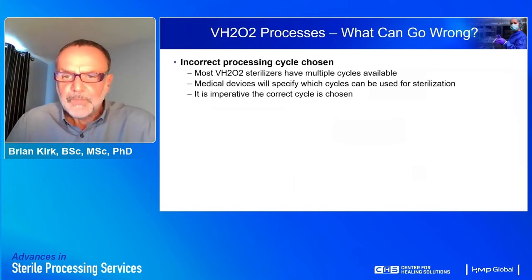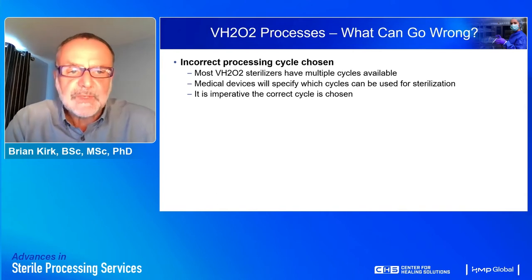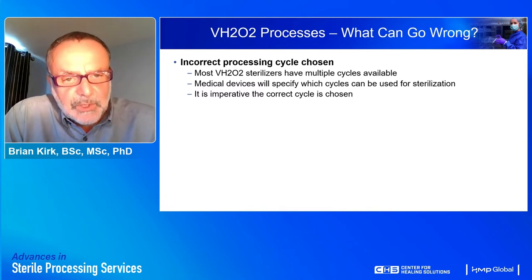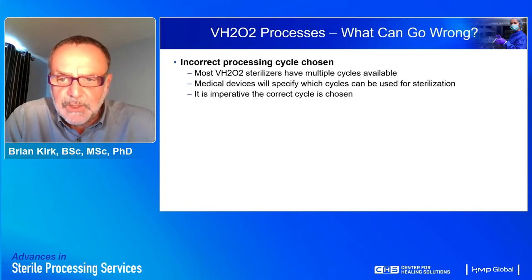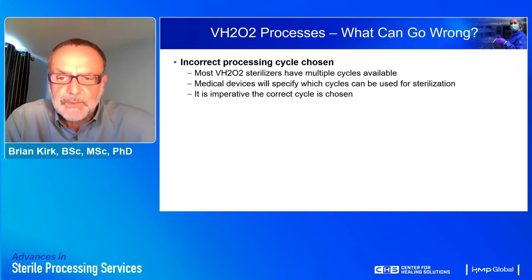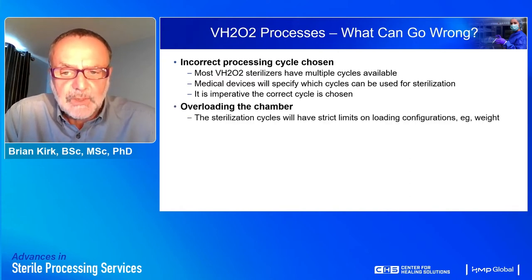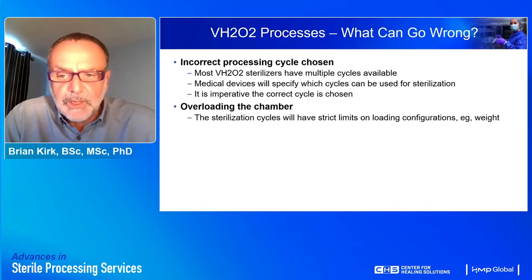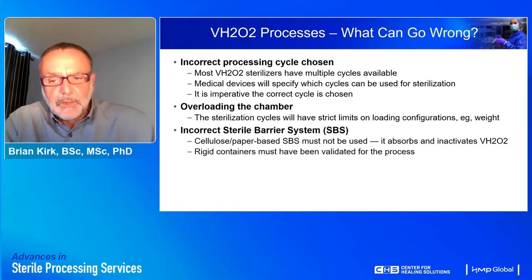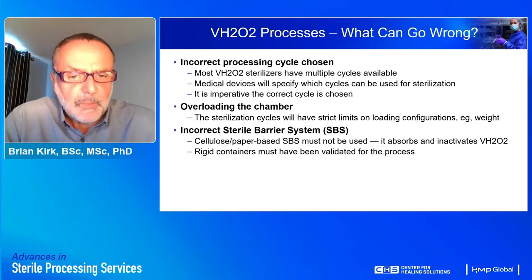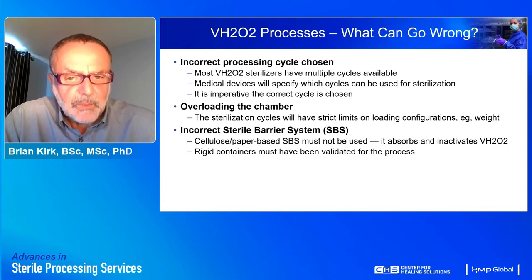What can go wrong? Most hydrogen peroxide sterilizers have several operating cycles built in, designed to process medical devices of different complexities — a short cycle for surface sterilization or a much longer cycle for a complex instrument like an endoscope. It's very important that the instructions accompanying both the medical device and the sterilizer are followed, that the chamber is not overloaded, and that instrument sets are positioned at the correct location. The sterile barrier system must not contain cellulose, because cellulosic paper-based packaging materials will absorb and inactivate hydrogen peroxide, preventing it from effectively killing microorganisms.